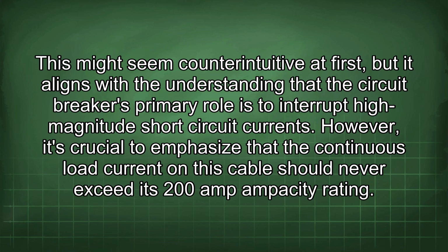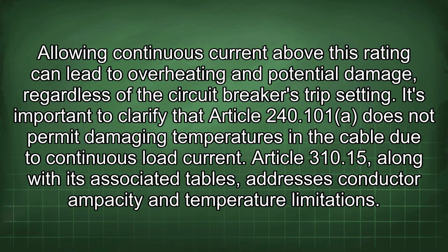However, it's crucial to emphasize that the continuous load current on this cable should never exceed its 200 amp ampacity rating. Allowing continuous current above this rating can lead to overheating and potential damage regardless of the circuit breaker's trip setting. It's important to clarify that Article 240.101 does not permit damaging temperatures in the cable due to continuous load current.